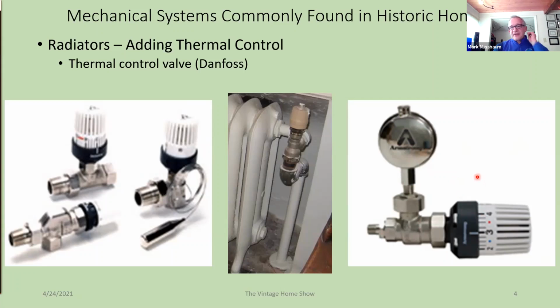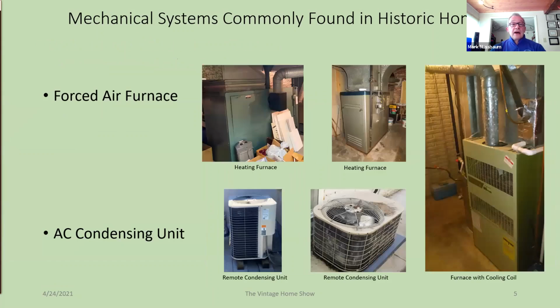Now, instead of controlling the steam coming in, I'm controlling it by slowing down the air leaving the radiator or stopping it from leaving the radiator. So this radiator will shut off if the space is satisfied. The way you do this is you put a thermostat for the system in the place that takes the longest to heat. Then you put these types of valves on your radiators in any space that's overheating, and then it'll keep it more comfortable, save energy, and make it more efficient.